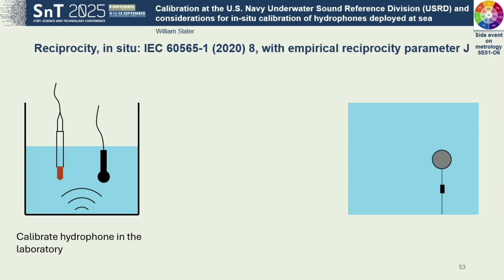The last method is an in situ reciprocity calibration that would require a new design of hydrophone to be deployed to the IMS. But note, this is not a primary calibration, even though it is reciprocity. In this method, a hydrophone assembly is built from 3 transducers. First, the hydrophone is calibrated in the lab by any method, and then it's built into an assembly with 2 projectors. At least one of the projectors must be reciprocal. Upon deployment, a reciprocity calibration is performed, except we know this hydrophone sensitivity, so we can solve for the unknown reciprocity parameter.